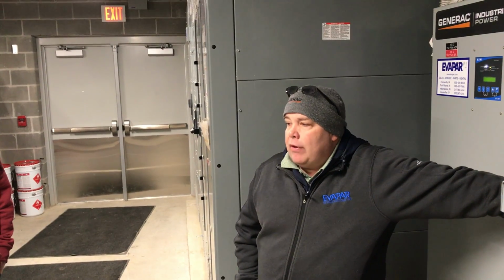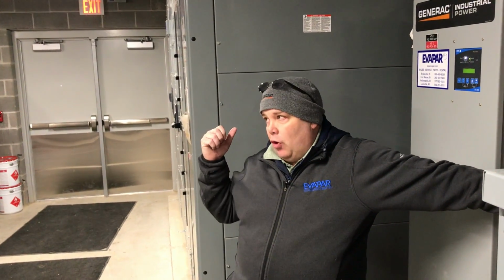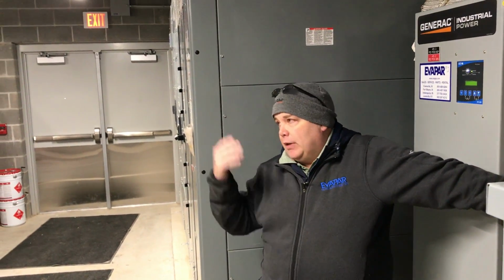Those two circuits feeding power out there, is it backed up by the generator? I'm gonna guess here, probably, about 99% sure. It's not really nothing more than, I don't want to say it's a nuisance, but it's not required. If that circuit feeding the battery charger, what happens, it transfers? That's what it says, battery.